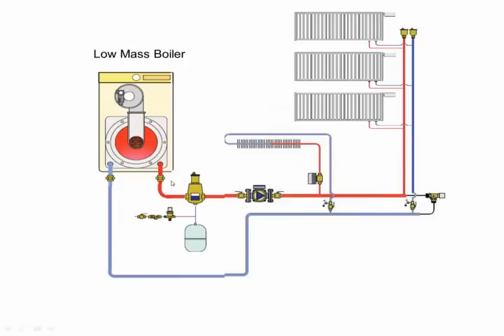Well, you might put it right here, because it's the lowest pressure point in the system, right, on the suction side of the pump, and at the highest temperature in the system, on the discharge of the boiler, okay? So everything's fine and happy here except for the boiler.